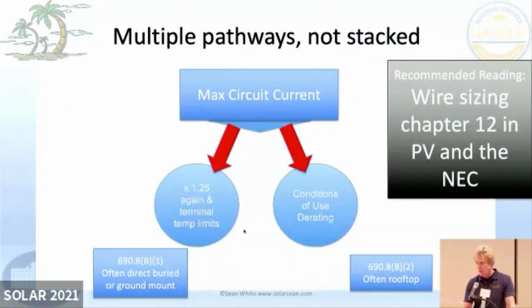Here's just a little bit about wire sizing. I mentioned I turned it into a 12-step process, but you've got your maximum circuit current. That's for the PV, that's short circuit current times 1.25. For everything else, that maximum circuit current is just like the label on the inverter, what it says. And then you do some stuff here, you do some stuff here, you compare the two different ways of doing it, and then you check it with this thing and you check it with that. There's a whole bunch of different checks. And I made it into 12 different steps how to do that.